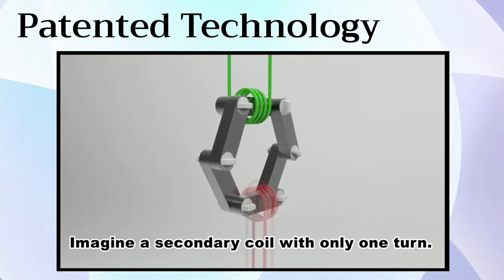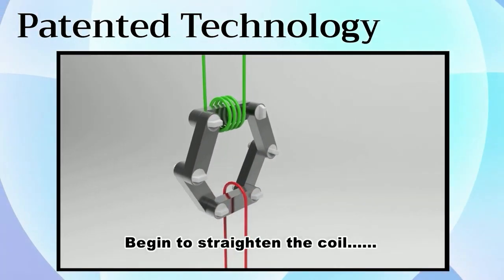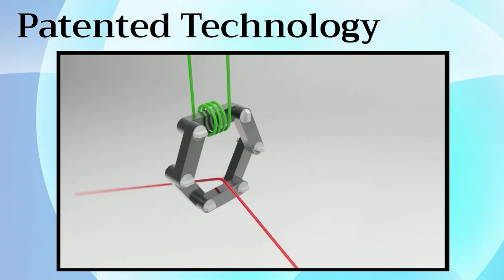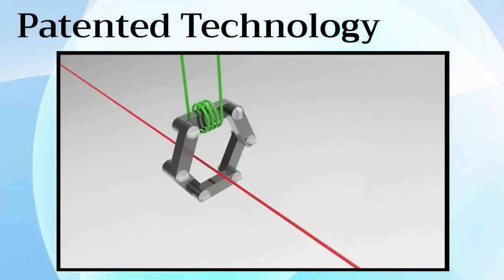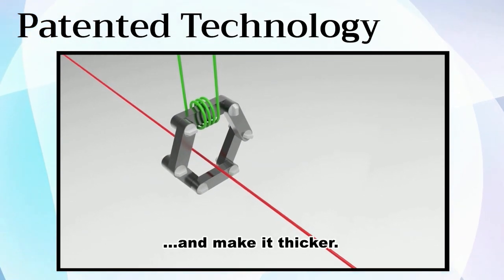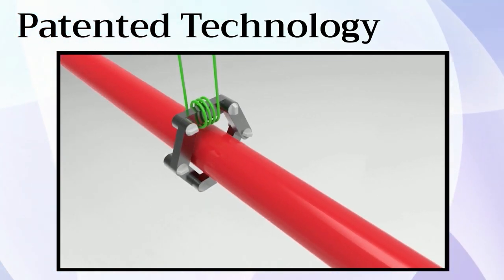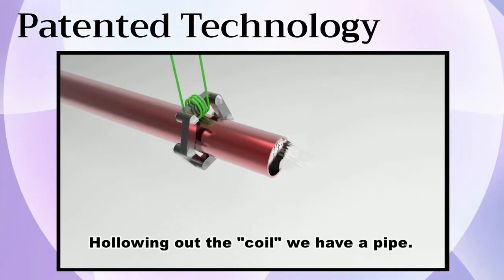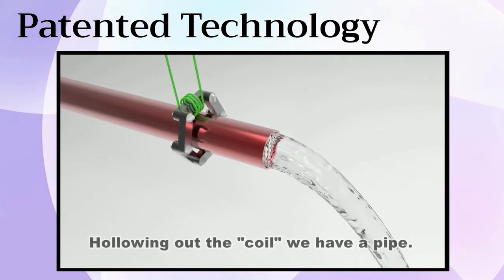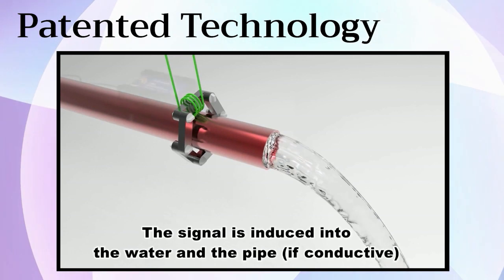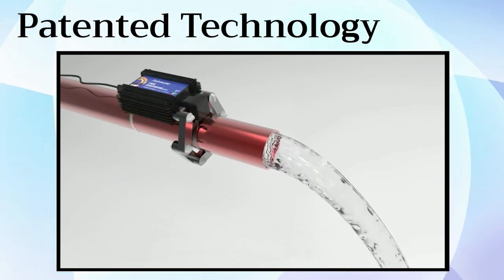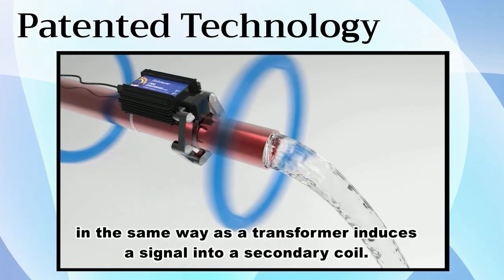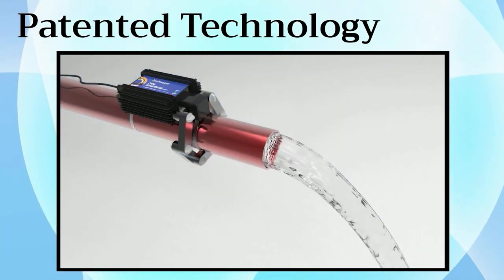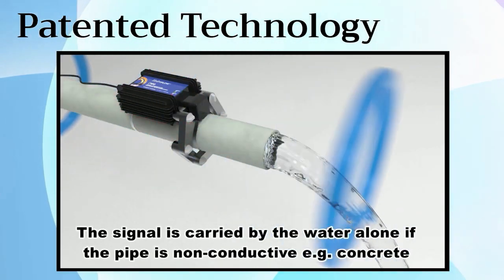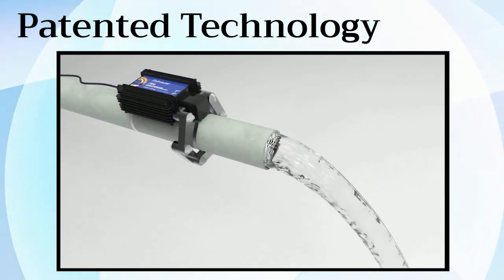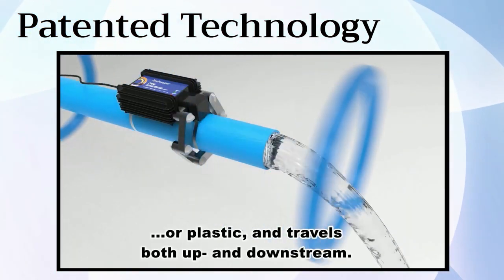Imagine a secondary coil with only one turn. Begin to straighten the coil. And make it thicker. Hollowing out the coil, we have a pipe. The signal is induced into the water and the pipe if conductive. In the same way, a transformer induces a signal into a secondary coil. The signal is carried by the water alone if the pipe is non-conductive, concrete or plastic for example, and travels both up and downstream.